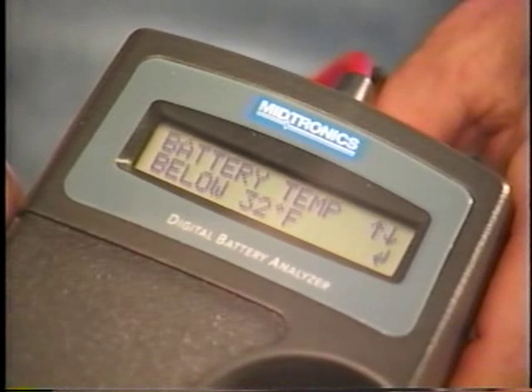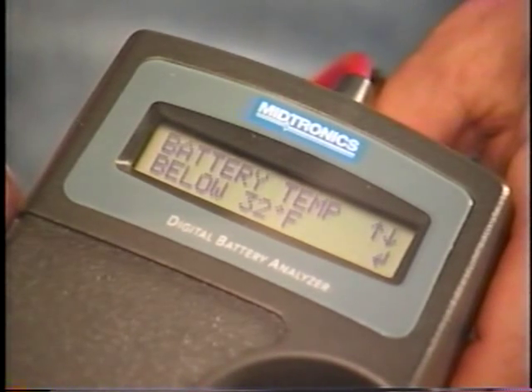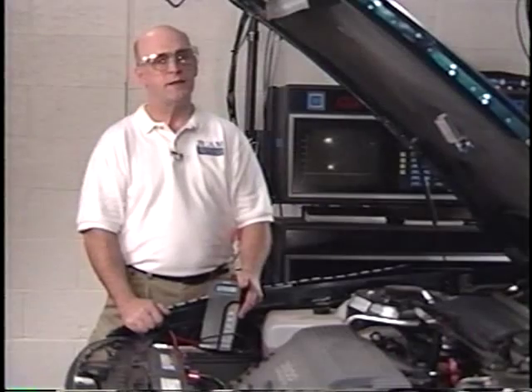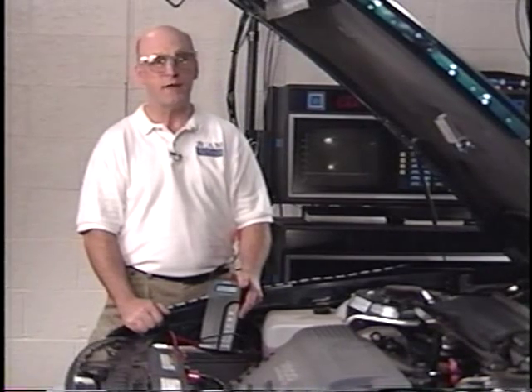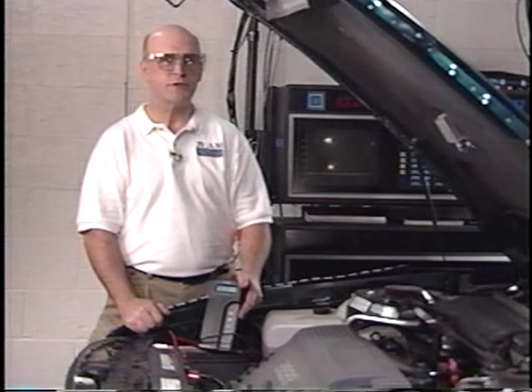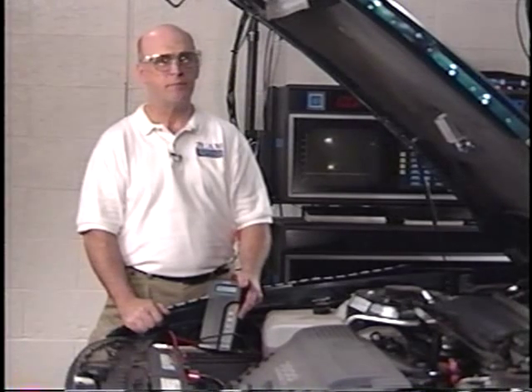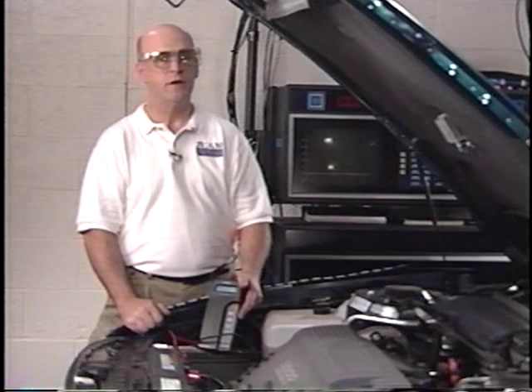One display message may be, is the battery above or below 32 degrees F? This message helps you avoid condemning a battery simply because it's cold. A cold battery cannot produce the same amount of energy as a warm battery. Simply indicate to the tester which condition the battery is in. If it's a warm battery, say above 32, and the test will proceed.